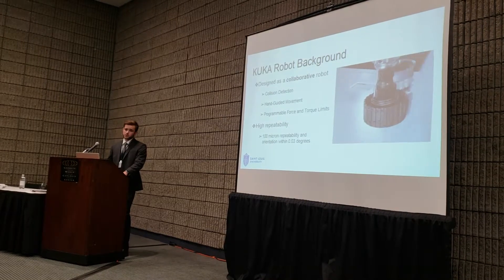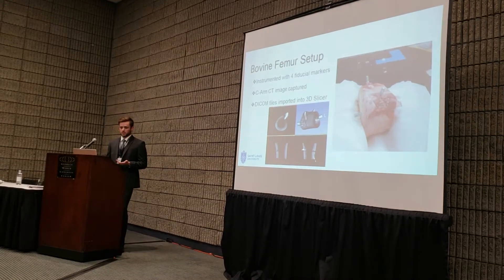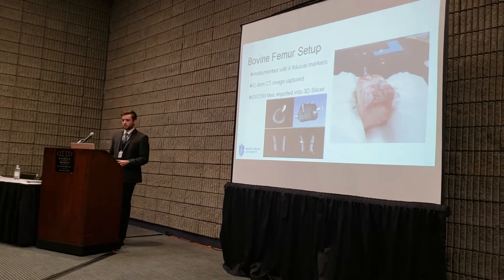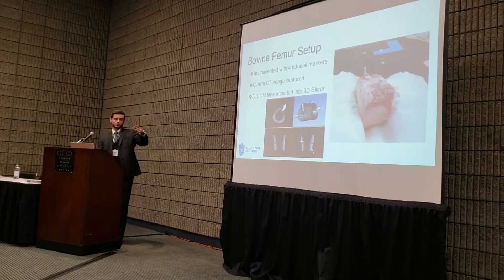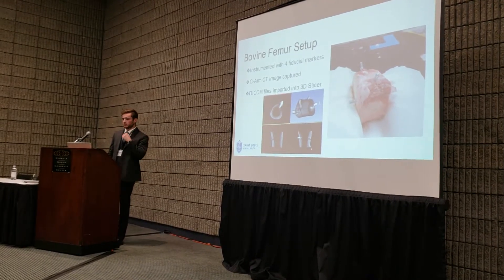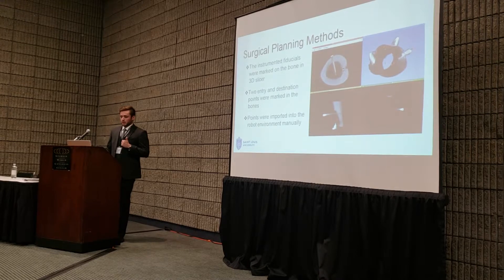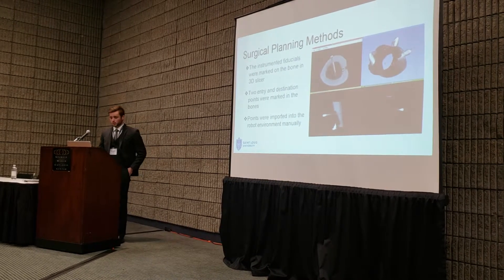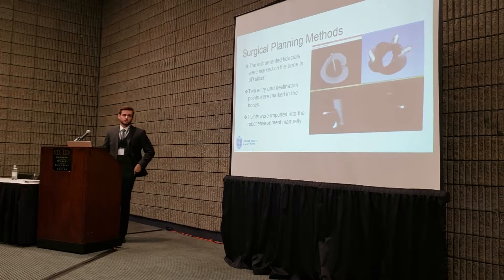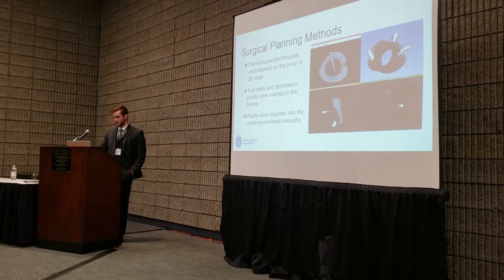The robot has about 100 micron repeatability and can place a tool repeatably within about 0.03 degrees. We set up bovine femurs to act as our spine. We needed four fiducial markers on each bone — three visible in front and one hidden behind. We used a C-Arm CT to capture the image, then imported DICOM files into 3D Slicer. We planned to place two screws per bone, identifying fiducial markers and placing entry and destination points for screw placement.